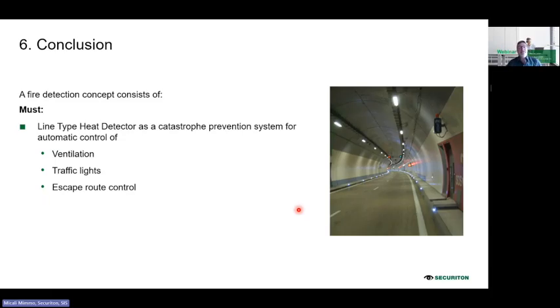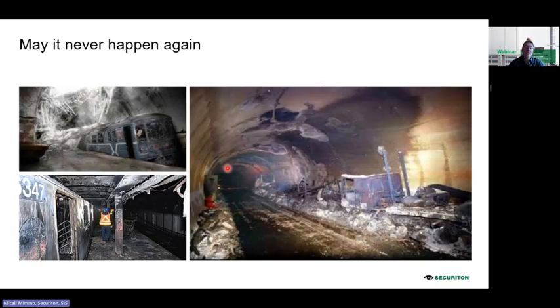Finally, the conclusion. Again, the fire detection system is a must for these tunnels. We call line type heat detectors a catastrophe prevention system, because it's the only system which will trigger in case of an alarm the ventilation, the traffic lights to avoid cars entering, and the escape route control. Therefore, it's a must to have fire detection inside the tunnels. And finally, to avoid the kind of accidents that we have had in the past, and from all we have learned about that, I think that when you have a fire detection system in a tunnel, most accidents can be avoided or kept to a minimum.